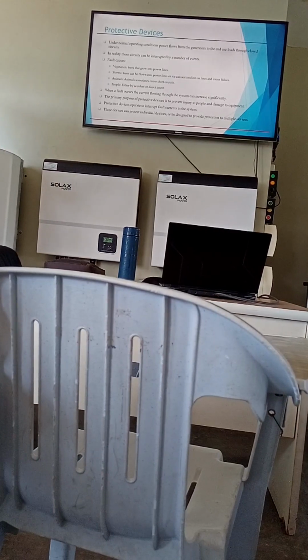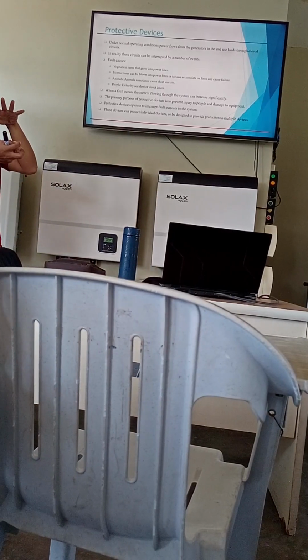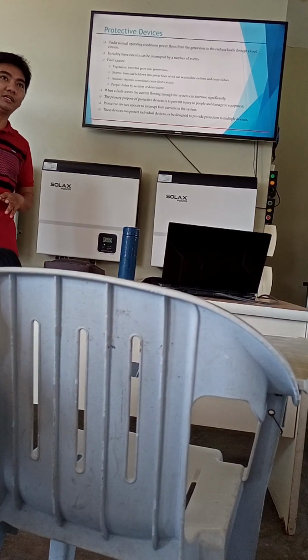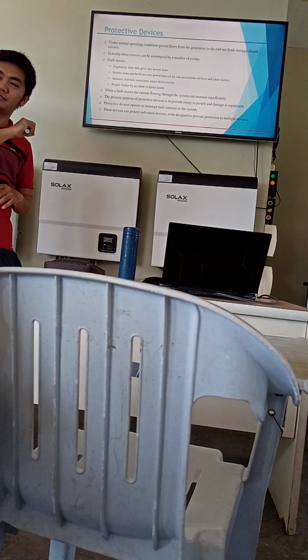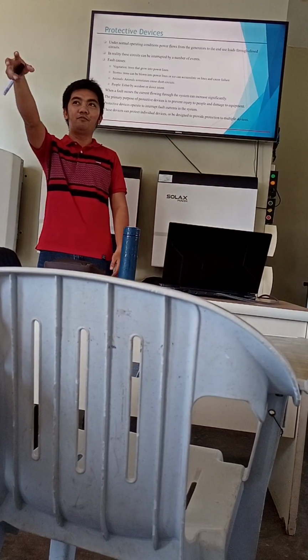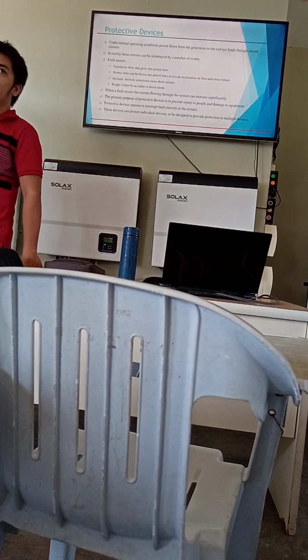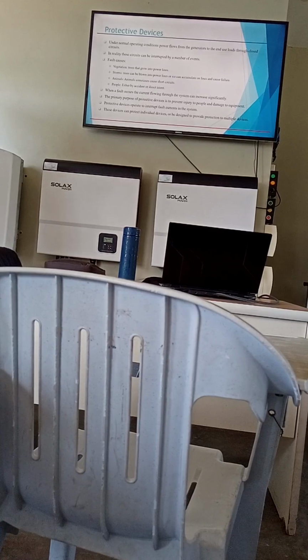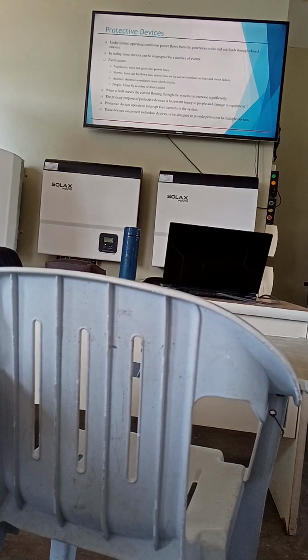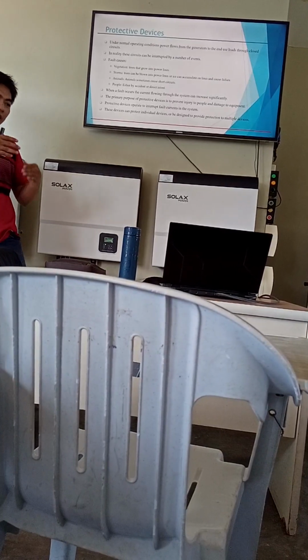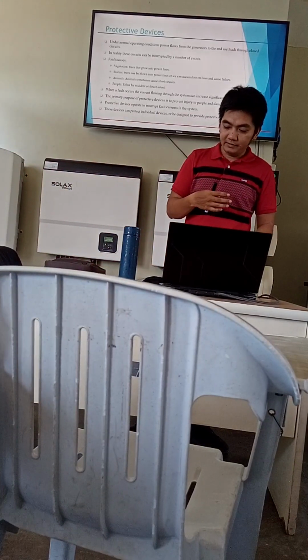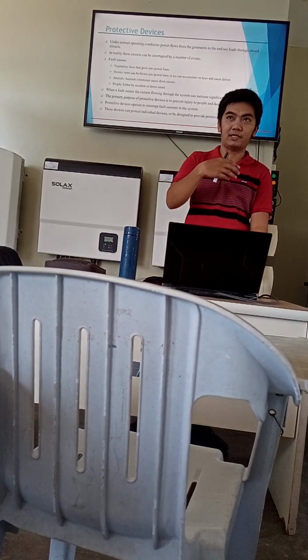So that is at the distribution level. But at the household level, it is cleared by either your home circuit breaker or your fuse. For example, if you plug in a fork, expect a brown out. The breakers are downstream protection devices. We have the circuit breakers in our own home, which trip if your inrush demand is too high. Second in line of protection is the cut-out fuse at your transformer, so that you do not affect your neighbor while they sleep. Then there is a set of redundant protections so that your faults do not cascade.